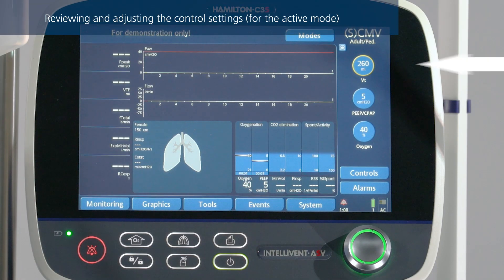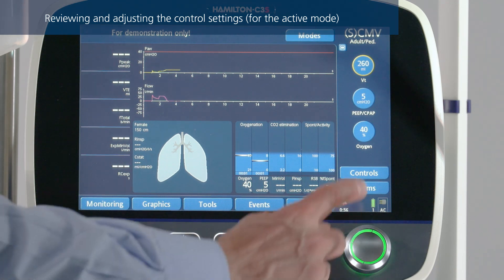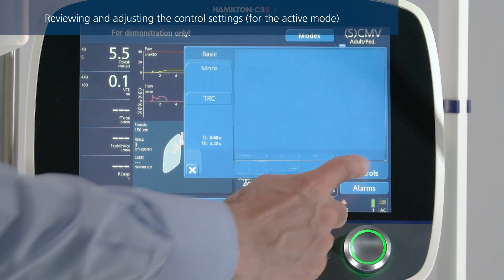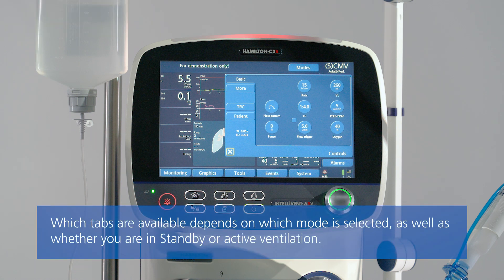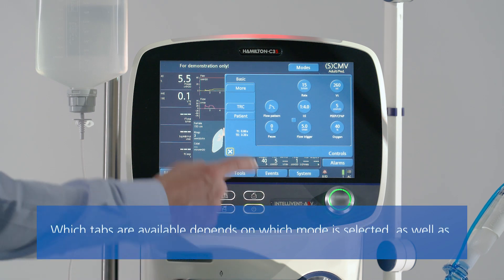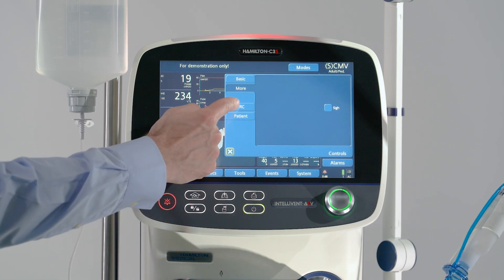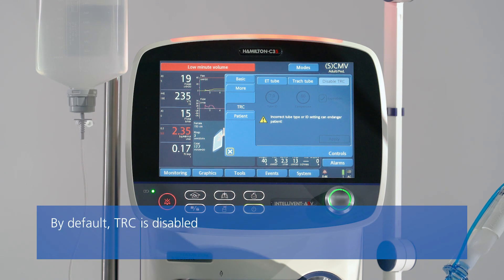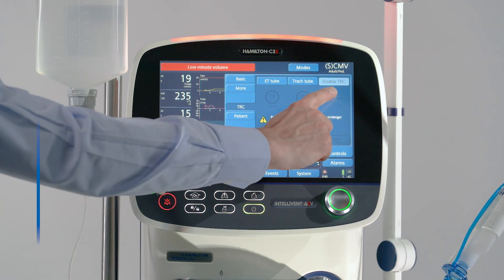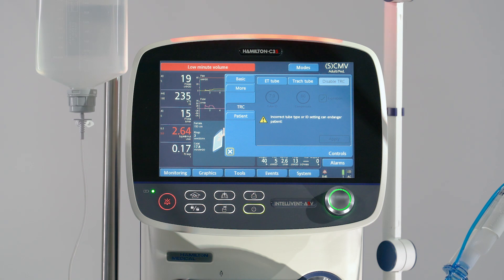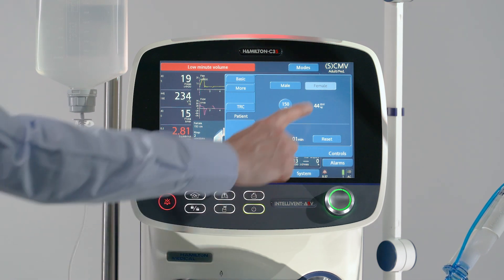To change any control settings, select and adjust the setting or touch Controls to access all the available settings. To enable or disable Sigh, touch More. To enable, disable, or adjust tube resistance compensation, touch TRC. If you need to change basic patient data, touch Patient and adjust the settings as needed.